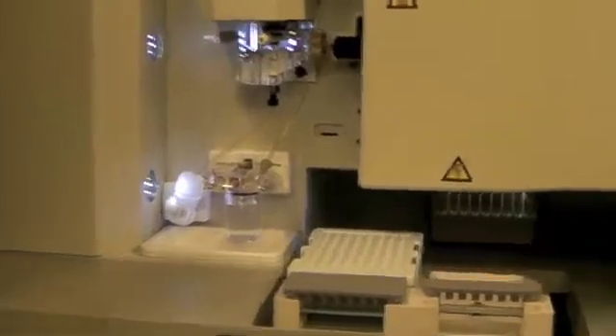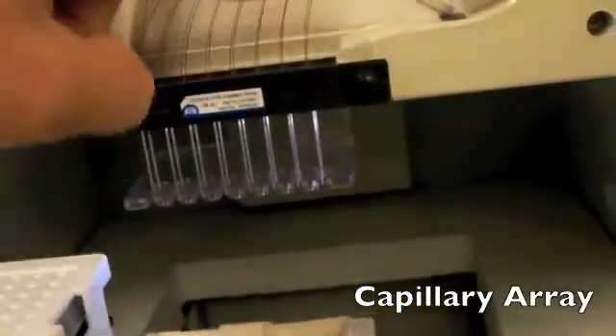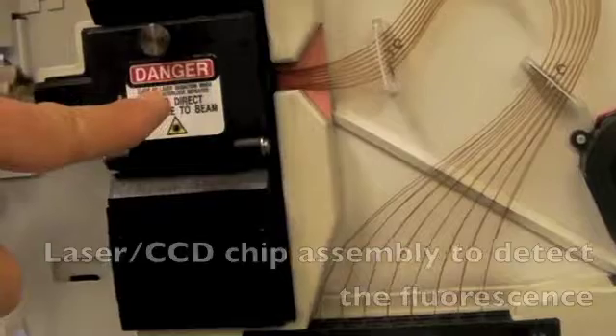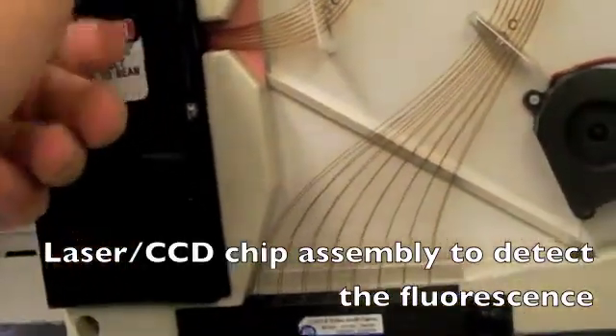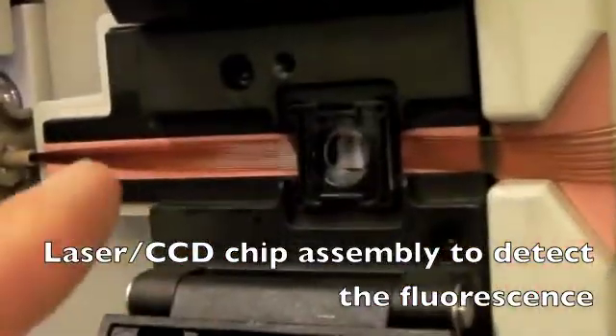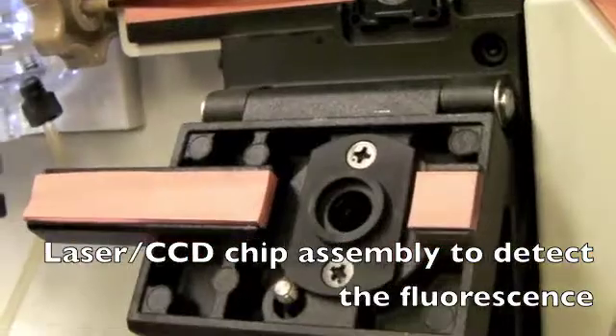Now what we have behind this door is our capillary array. See those fine little needles? These are injection needles where those samples are going to be taken up. The samples will then travel through those fine tubes called the capillaries until they get to the little window where they will be irradiated by a powerful laser and the fluorescence given off is detected and recorded.